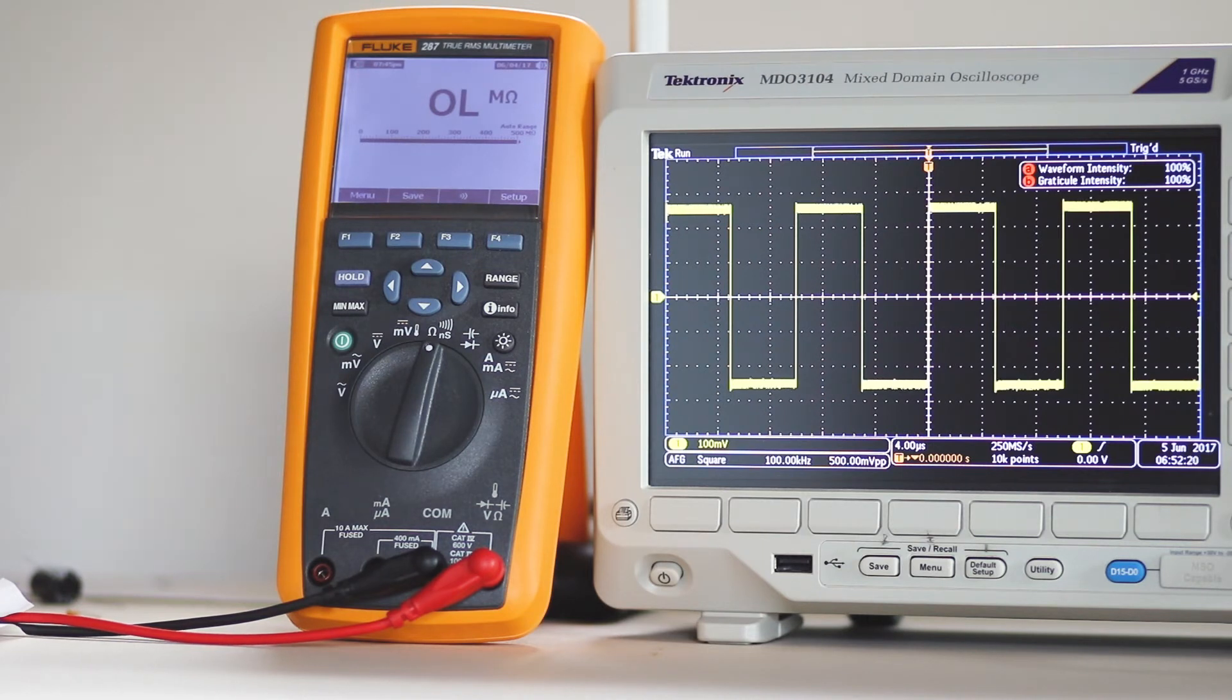If these types of measurements are not sufficient for your application, the next step up is an LCR meter. Using this instrument, the procedure is the same as for the multimeter in capacitance mode. Just clip onto the leads and take the reading.